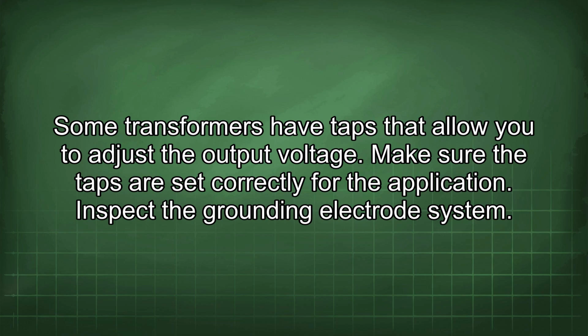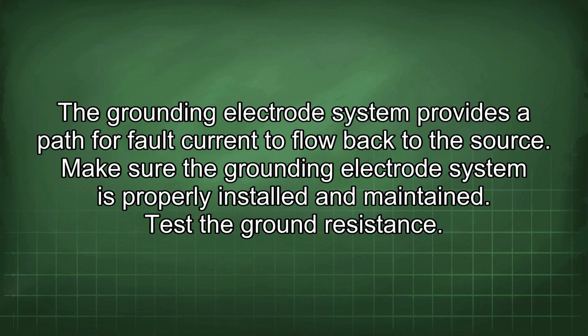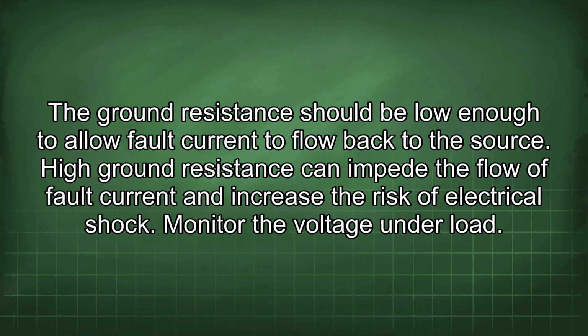Inspect the grounding electrode system. The grounding electrode system provides a path for fault current to flow back to the source. Make sure the grounding electrode system is properly installed and maintained. Test the ground resistance. The ground resistance should be low enough to allow fault current to flow back to the source. High ground resistance can impede the flow of fault current and increase the risk of electrical shock.